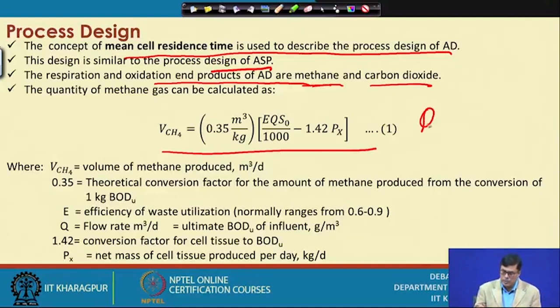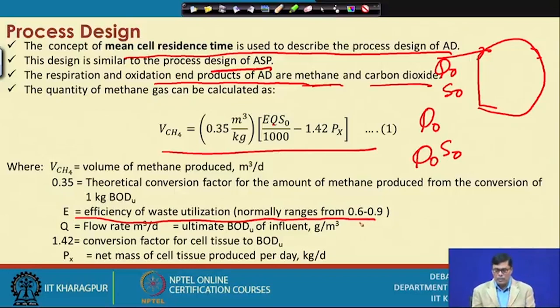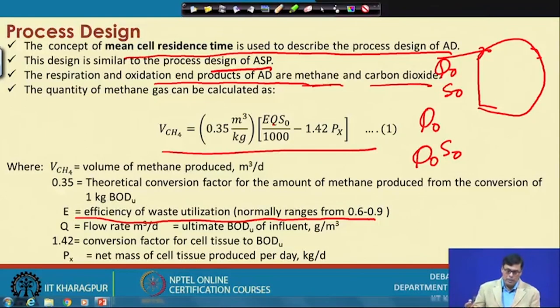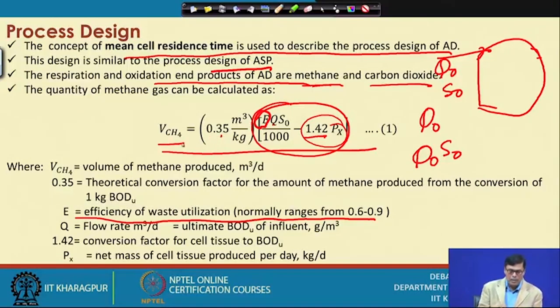In the key design equation: Q₀ (or Q) is the incoming flow rate of the digester, S₀ is the input substrate concentration, so Q₀·S₀ is the input substrate load. E is the efficiency of waste utilization, normally ranging from 0.6 to 0.9 — meaning 60 to 90 percent of organic matter can be converted. Deducting the fraction converted to cell mass gives the actual BOD removed, and multiplying by 0.35 gives the volume of methane produced in cubic meters.